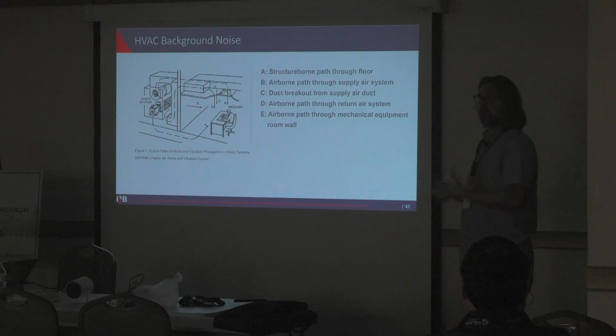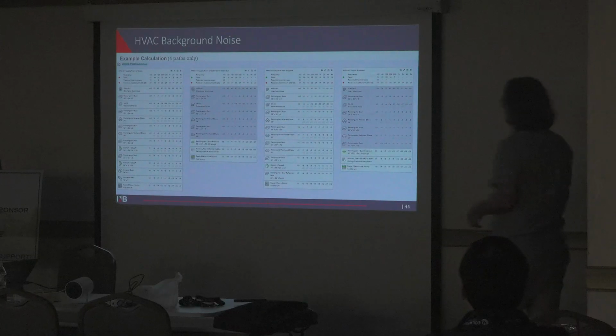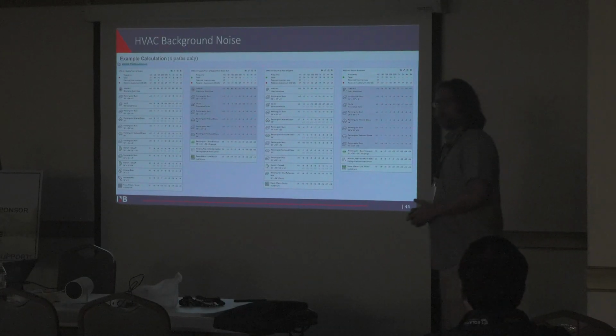So the NC30 goals that are listed are the total room's final requirements, not from an individual path, which is something to always make sure of. So for me, if I need an NC30 space, I design the path to 25, and then when 4 or 5 of those sum together, they kind of meet NC30 in the end. Here's an example of those path calculations. We literally take the mechanical plans and the drawings, and we start with the data that the manufacturers provide.